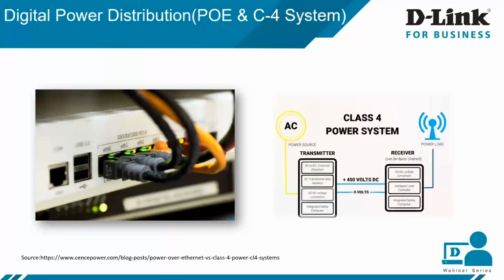It will immediately stop the flow of power, almost instantly within a few milliseconds, if any predefined fault is detected. That's why it's also called a fault managed power system. Although each class 4 power system uses its own technology to fulfill this requirement, certain class 4 systems may achieve this using integrated sensors or intelligent software.